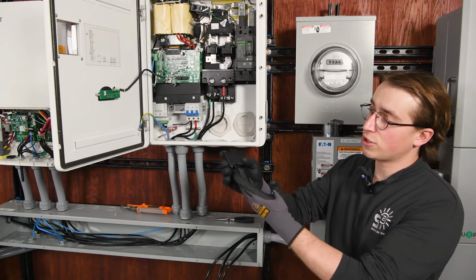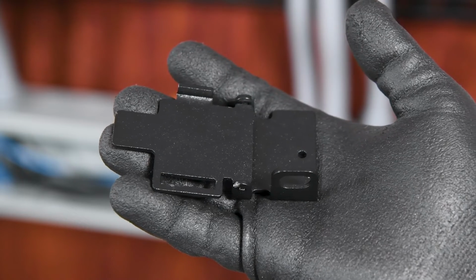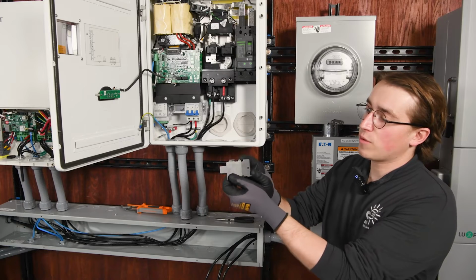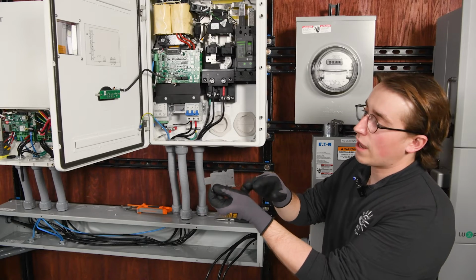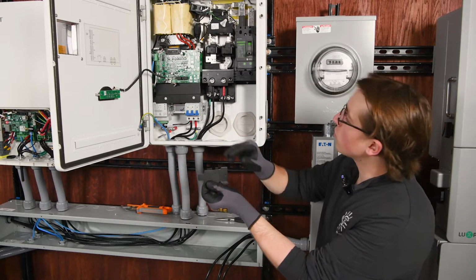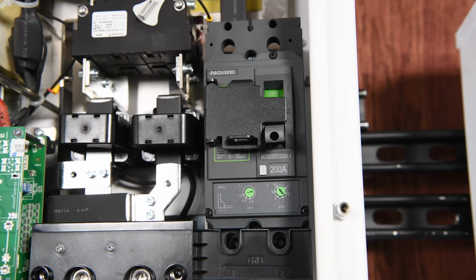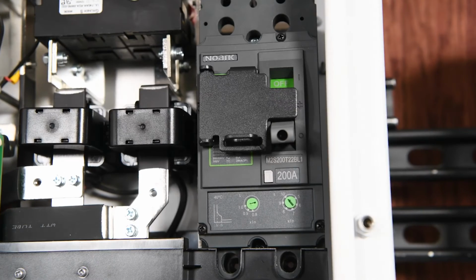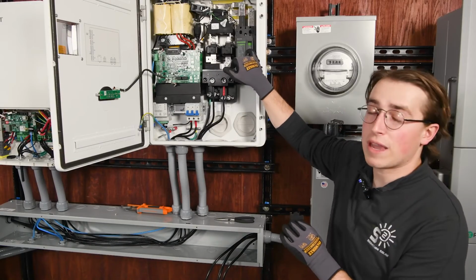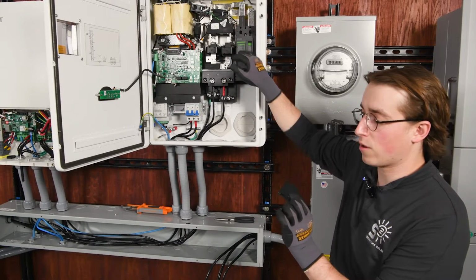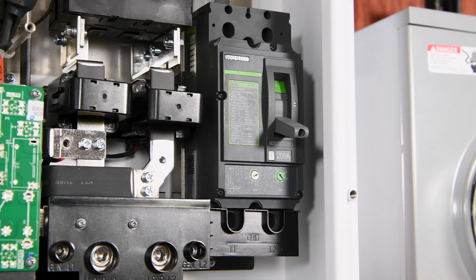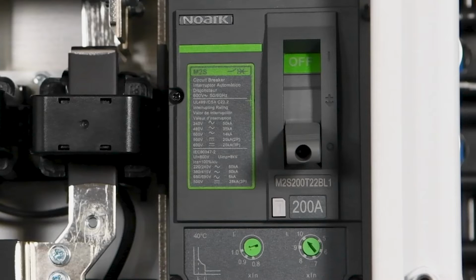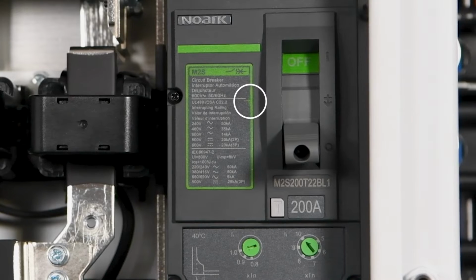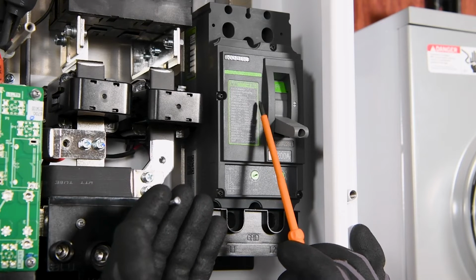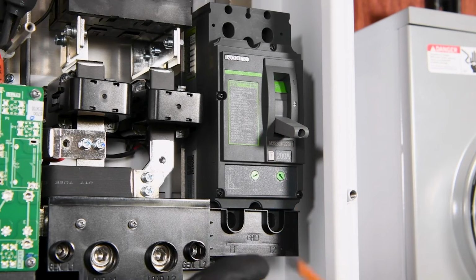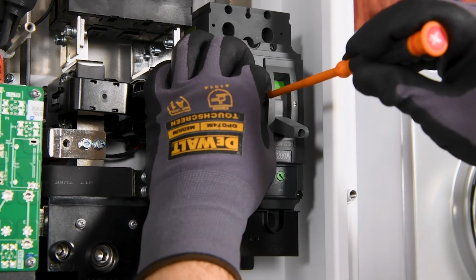Included with the SYN packaging, we have a breaker lockout kit. Now, this is going to be manually installed by us, and what we'll do is take the single screw that comes with it and secure it to the breaker itself. This is essential for lockout tagout procedures where you need to ensure that the main service feed does not get powered on without your permission. To install the breaker lockout kit, there is a small green cross, and we will take the included screw and secure the lockout kit by inserting the screw on the cross itself.